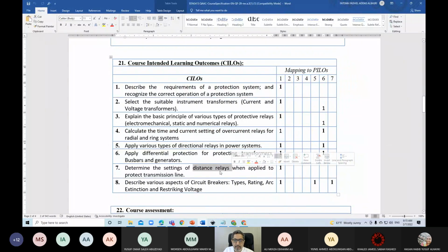Later, we'll cover the distance protection principles. Distance protection is normally used to protect transmission lines. However, these are based on measurements of the impedance of the line, and if the impedance measured by this relay is smaller than the impedance of the line, fault is declared inside the line.